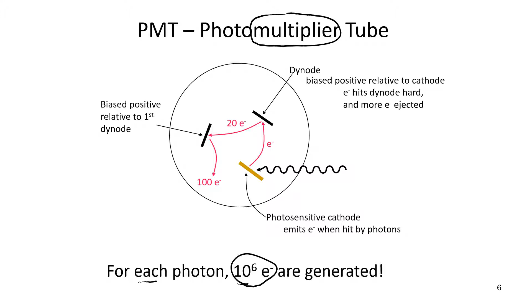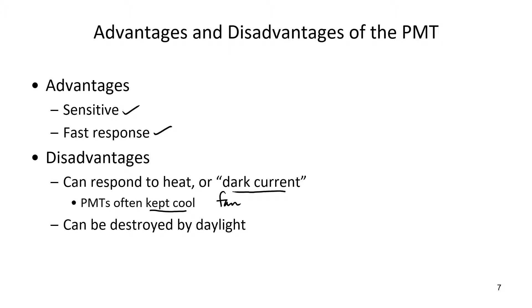So the advantages of a PMT is that it's sensitive and fast, but there are some disadvantages. Sometimes these PMTs respond to heat, not light, just heat. So if you've ever used an instrument, you may have noticed that as soon as you turn it on, you hear a fan. And that's to keep it cool so that it doesn't respond to heat, and we like to call that dark current. And another disadvantage is that, yes, although it's sensitive, maybe it's a little bit too sensitive, given that it can be destroyed by daylight. So that's the PMT. Hope you enjoyed the video, and thanks for listening.